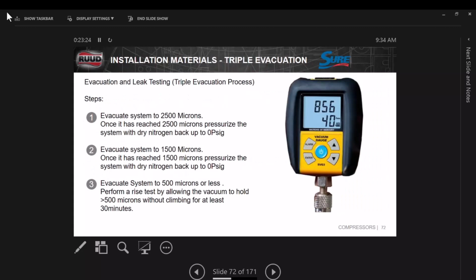It's in there. Hopefully we have one of these on there. This is not a television. This is a micron gauge. If we're not using micron gauges, guys, we're way, way in the past. I mean, we've got to use these things. We've got to get it down to 500 microns, knowing that we have all the moisture out.